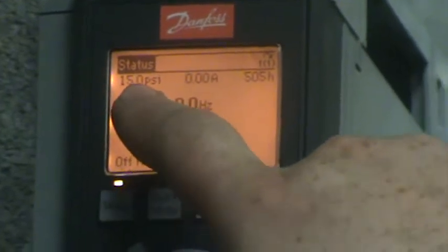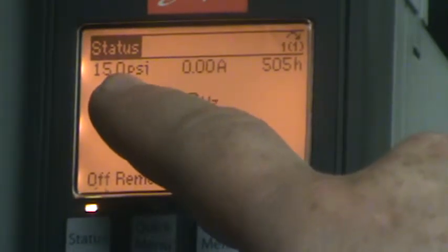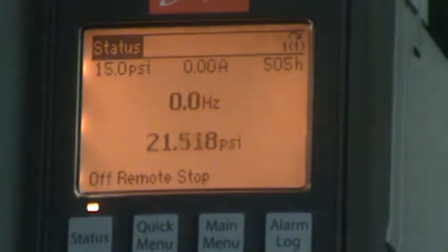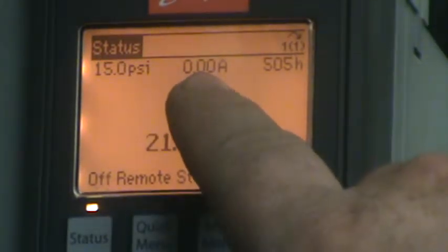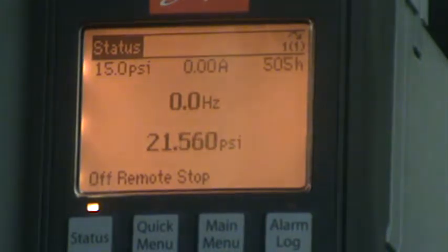Okay. Up on the drive screen here, the upper left-hand corner is just a statement of what the set point is. Okay, right now we have them set at 15 PSI differential. You guys are probably going to adjust that over time when you see what your building's doing. The middle numbers here, which are currently zeroed out, is the motor amperage. When the motor's running, it takes all three phases, averages them out, and displays it. Gives you guys an idea how well the motor's running based off of, you know, what it should be.